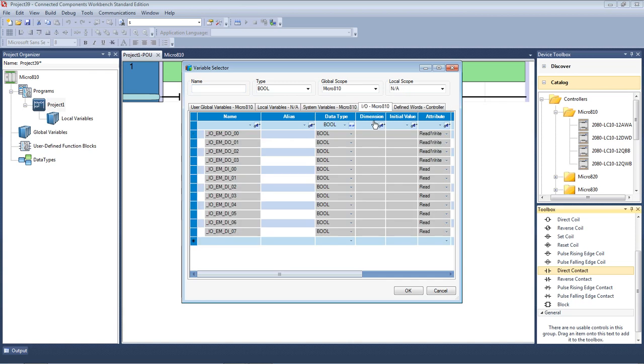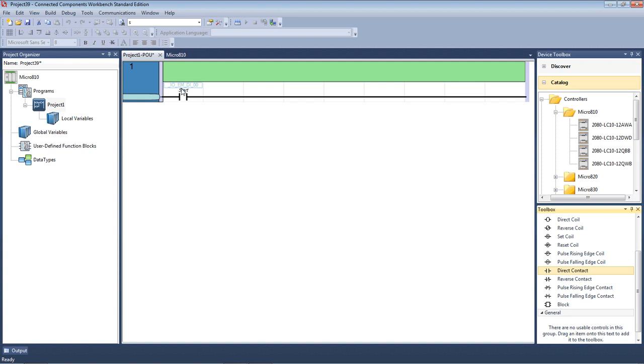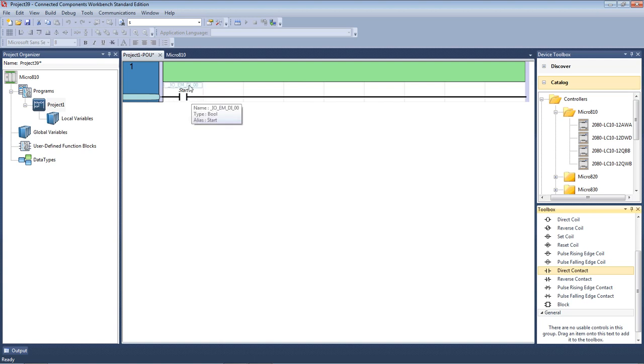If I click on the input-output here, I've got input-output micro 810. It gives me the listing of my four outputs, my relay outputs, 00 to 03, and my eight inputs. So it's DO for output and DI for input. So 00 to 07 is my eight inputs. I'll select my first input, I'll give it a name, my start, I'll just give it a start button. What it does, it addresses that element there to say that if I put a 24 volt signal onto my first input, 00, it'll tell the logic to come along, come into the logic here and close that element of the rung.